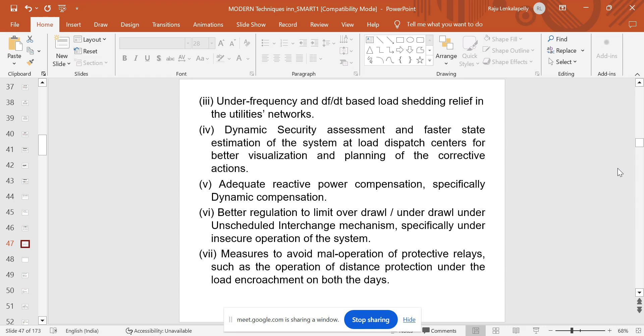The most important suggestion by the committee is deployment of adequate synchrophasor-based wide area monitoring systems and system protection systems. As of today, in place of SCADA, it is better to have a synchrophasor or PMU - both are the same. With regular data systems there is sometimes a time delay between measurements, but with a synchrophasor, all measurements come with respect to a common time reference - that's why it's called synchrophasor or phasor measurement unit. By using PMUs we can monitor, protect, and do everything.